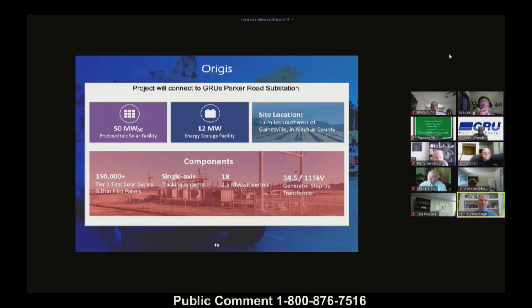Here are some figures of merit for the project. It is 50 megawatts AC, with a 12 megawatt battery and 2 hours of storage. It will be located south of the Parker Road substation, at the corner of Archer Road and Parker Road. It will have single axis tracking, so the panels tilt and follow the sun across the sky. There will be more than 150,000 solar panels, with a step-up transformer from 34.5 thousand volts to 115,000 volts to connect to GRU's transmission system at Parker Road.